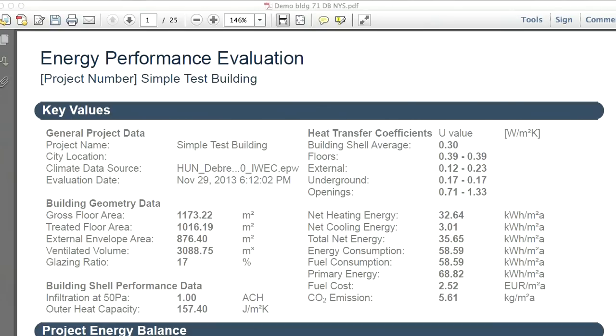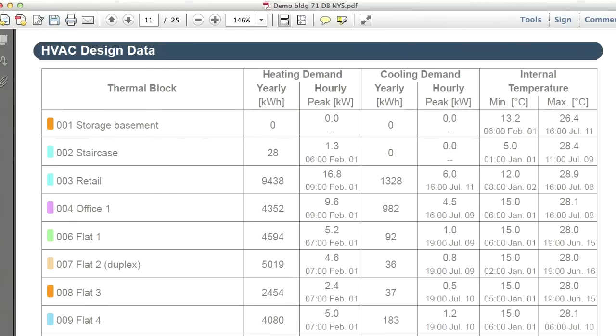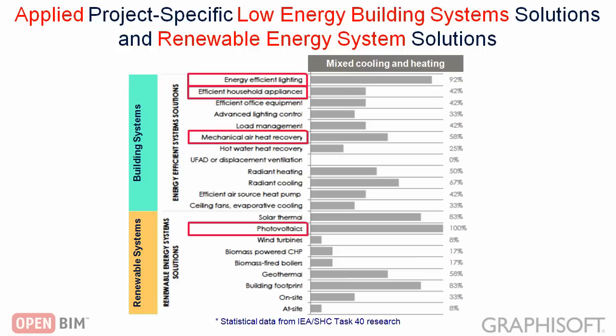The lower heat transfer coefficient values on the Energy Evaluation Report reflect the benefits of the project-specific energy efficient architectural solutions, such as the advanced envelope and detail construction as well as the advanced windows. Due to solar shading, the solar heat gain is significantly less during the hot season and therefore the cooling demand is also less compared to the baseline building. The HVAC Design Data Chapter contains the initial input information necessary for the sizing of the building systems — the annual and hourly peak heating and cooling demands. The workflow of how to select the project-specific low energy building system solutions is quite similar to the architectural solutions workflow.